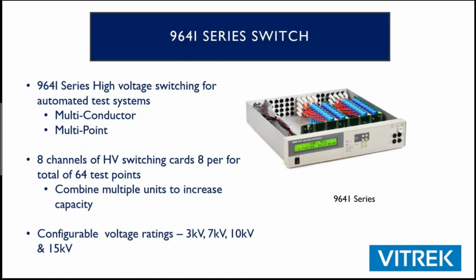So an extension to any of our HIPOT testers is the 964i switch. This can be fitted with high voltage or high current relays. And it's great for multi-product test applications, in a situation where, let's say they have a 60-second test, and you don't really want the operator to have to sit around for 60 seconds between products they hook up. So you could hook up, I don't know, 10 products, 20 products to a 964, press the start button and walk away, and that operator could go be productive for 10, 15 minutes, and then come back to a batch of products, switch those out to the next batch, press the button, and then go be productive again.